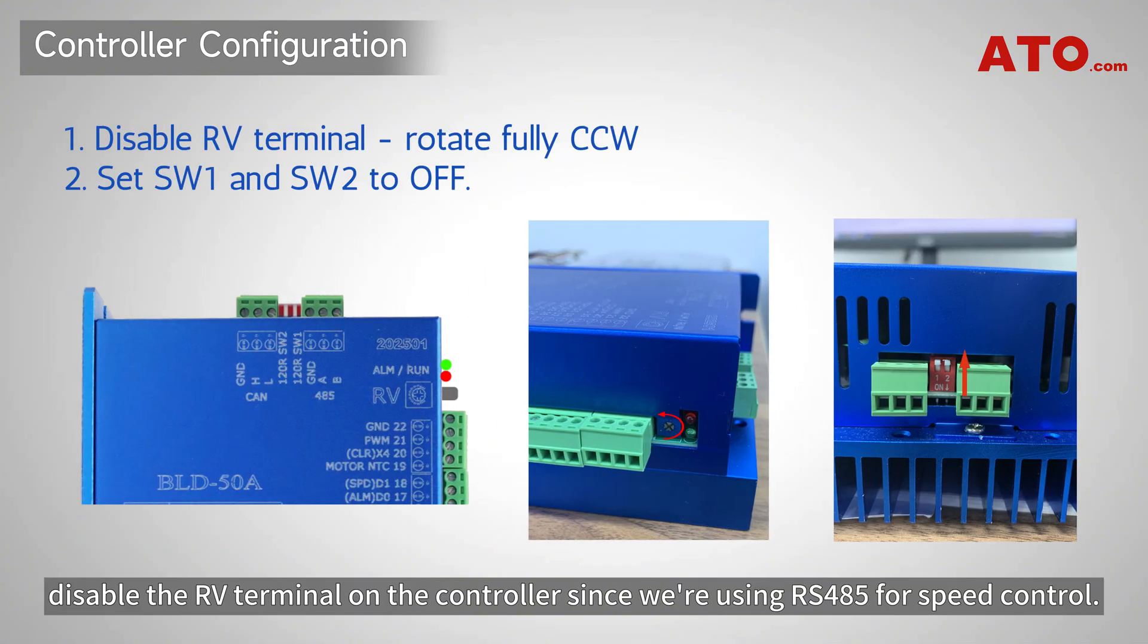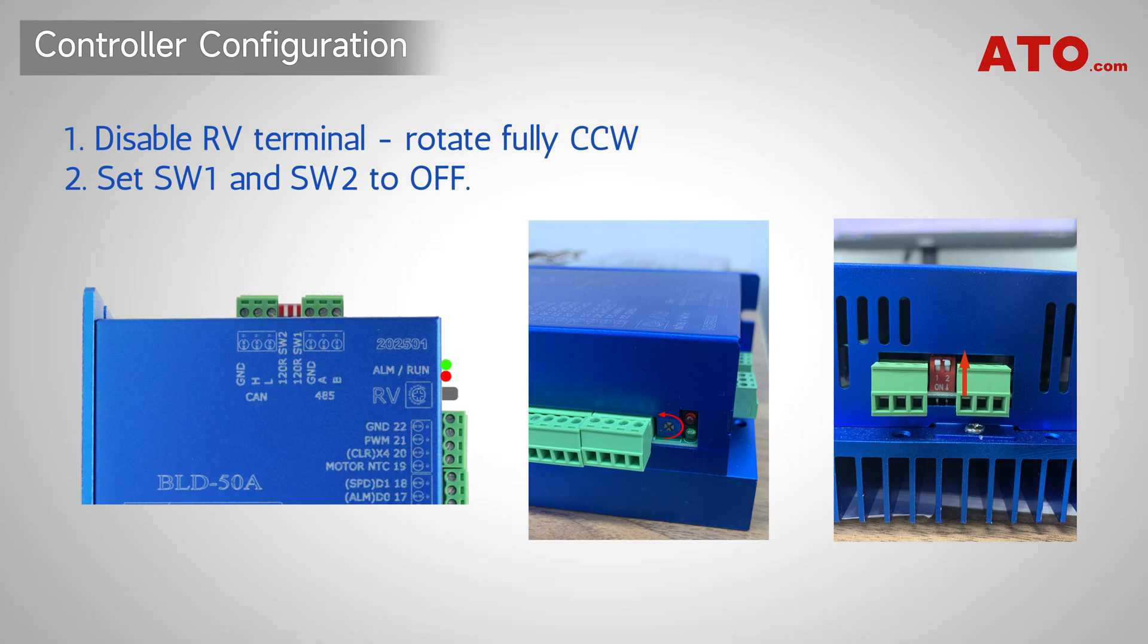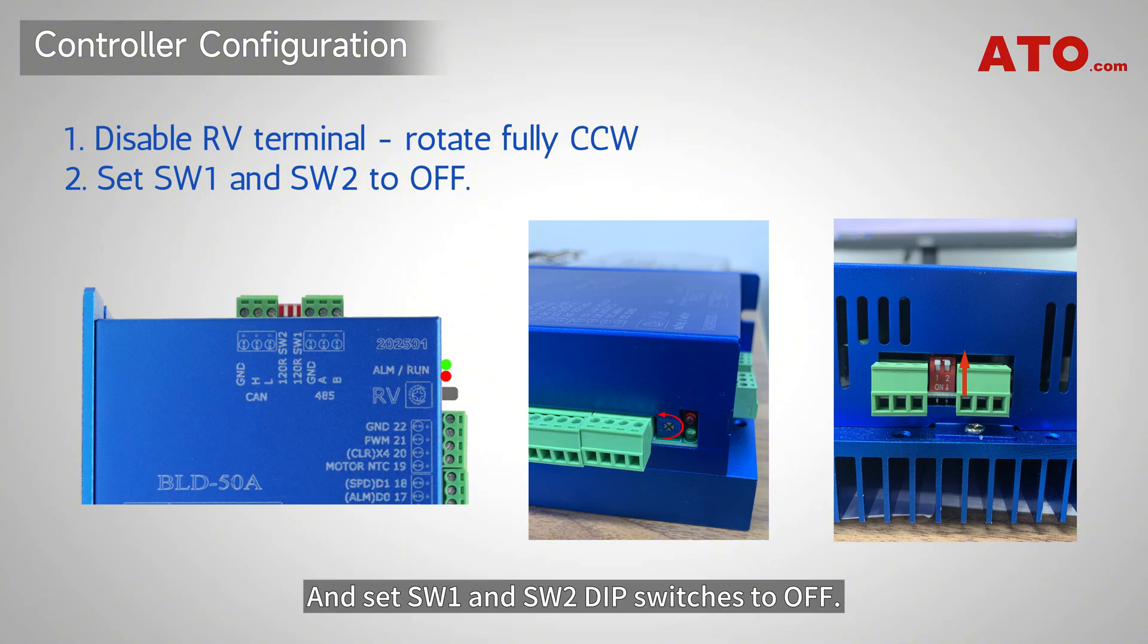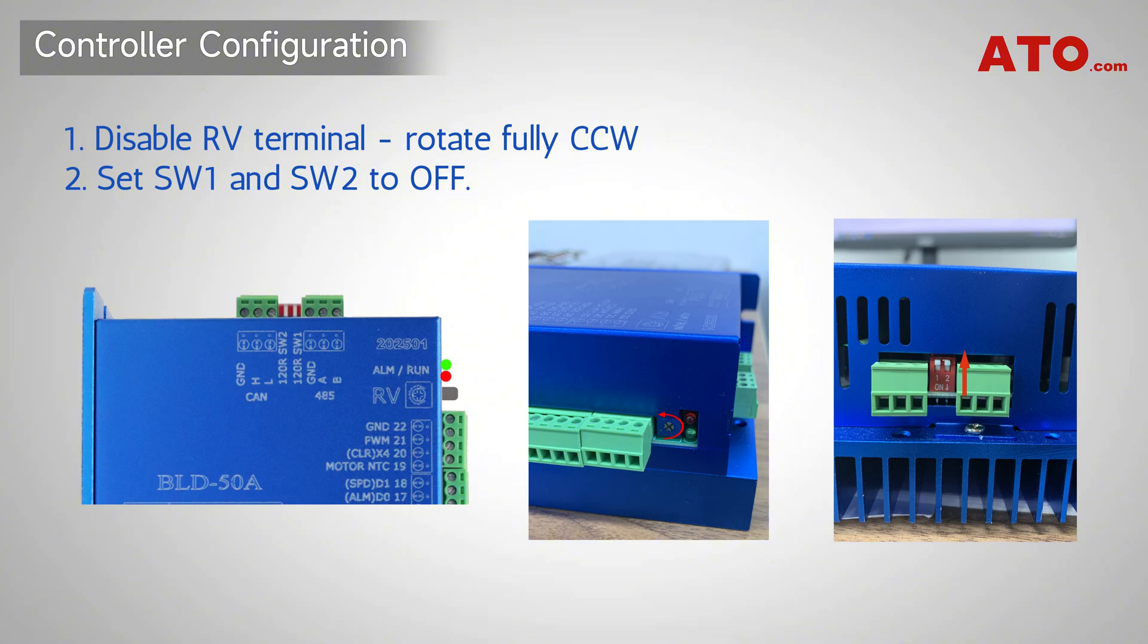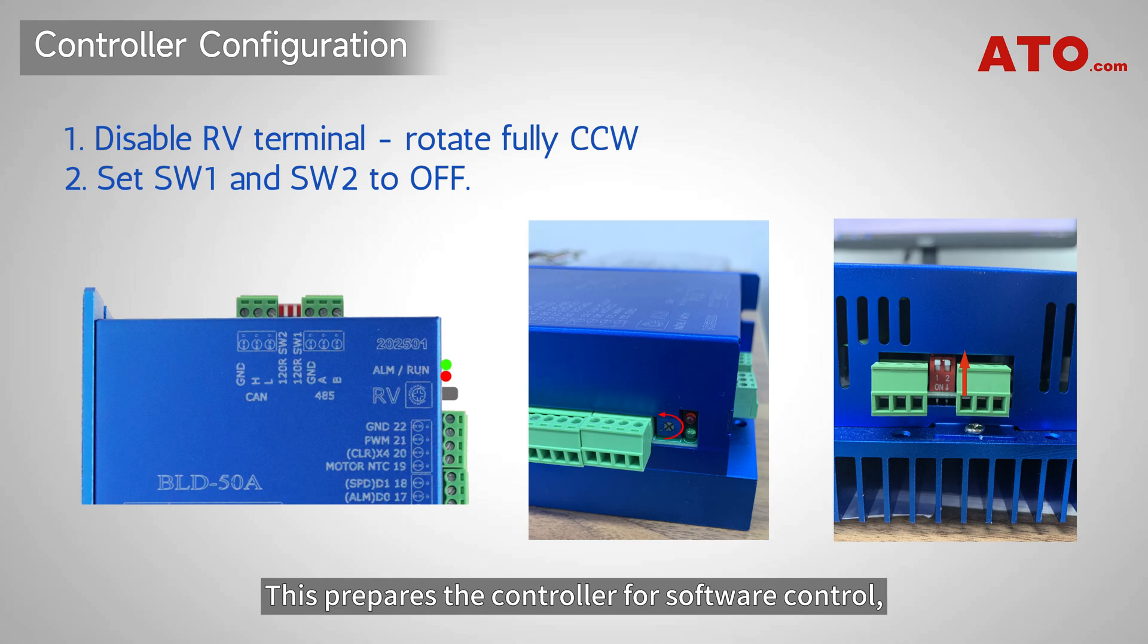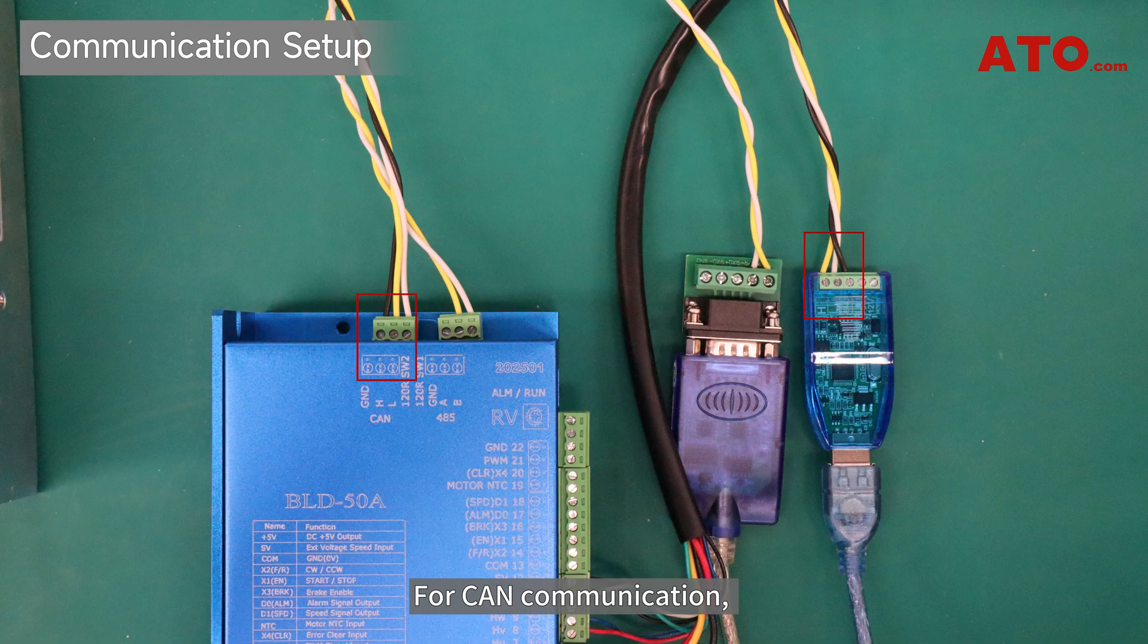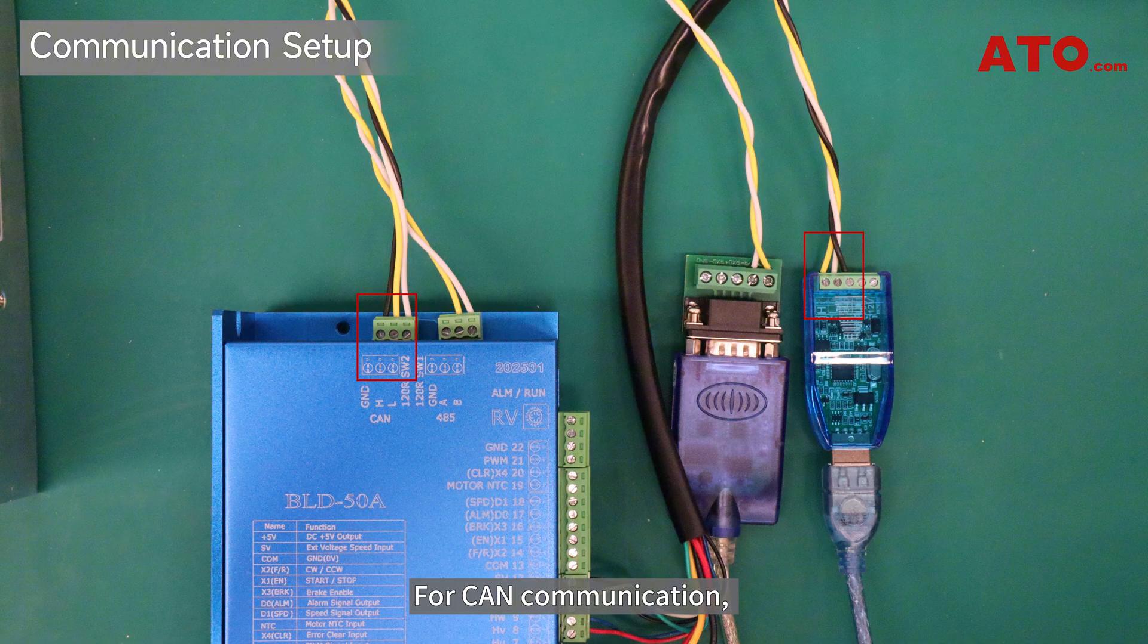Before proceeding, disable the RV terminal on the controller since we're using RS-485 for speed control. We don't need manual potentiometer control. Set SW1 and SW2 dip switches to off. This prepares the controller for software control, not manual adjustments.